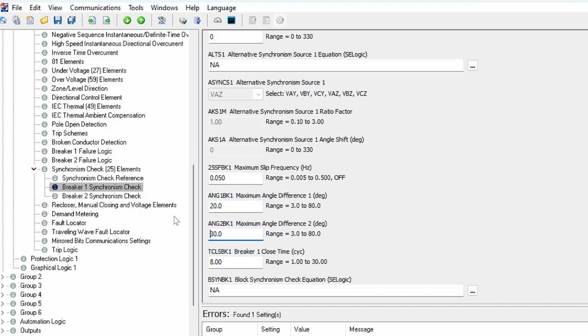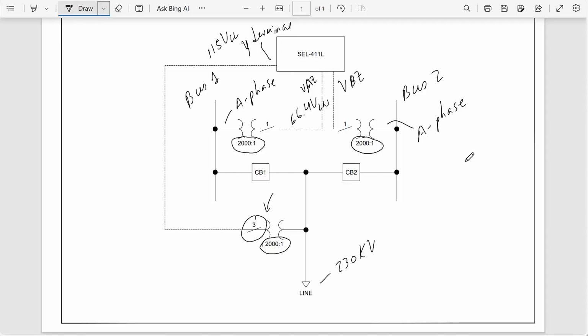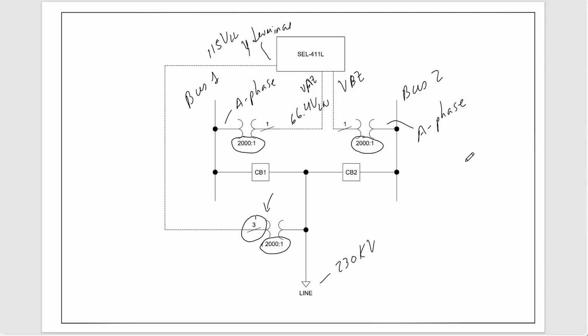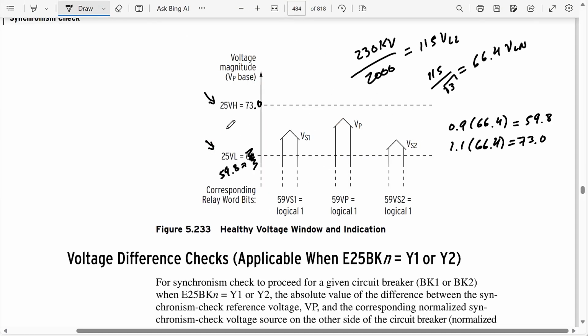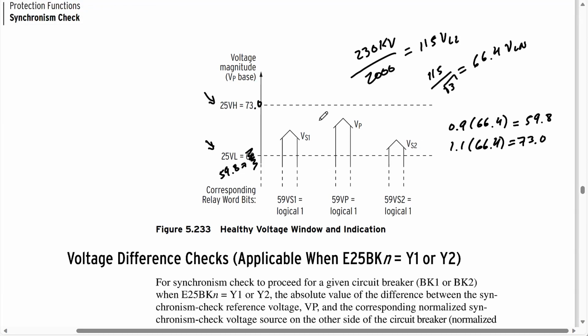Now to summarize this a little bit, let's go back to the one line. And so here we said that we're comparing the line side A phase voltage, which is what we're calling the reference, and we're comparing that to the A phase to neutral voltage from the bus side. And for the relay to declare the two voltages to be in synchronism, they have to be within the band that we define in the settings. Again, that's basically this over here. We have to be within this band, and we define that to be plus or minus 10% of the nominal voltage, which in our case is 66.4 volts. So that band is going to be from 59.8 volts up to 73 volts.